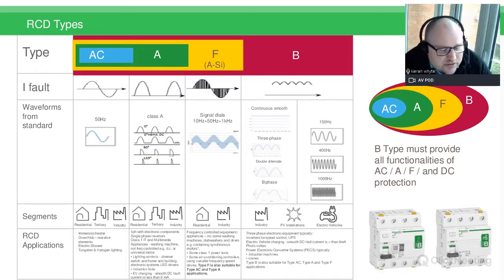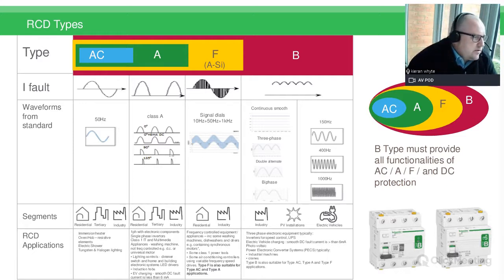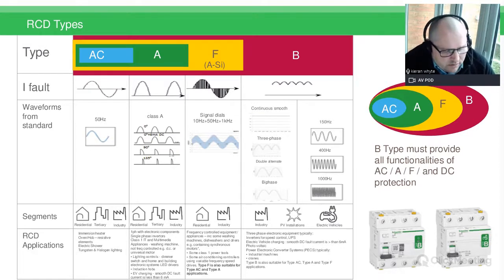Now the industry is moving more towards the A type, and the A type will do exactly the same as the AC type, but it will still operate effectively with up to 6 milliamps of DC current on the line as well. Then we get into a more specific type of RCD, the F type, or in Schneider's range it is called the ASI.